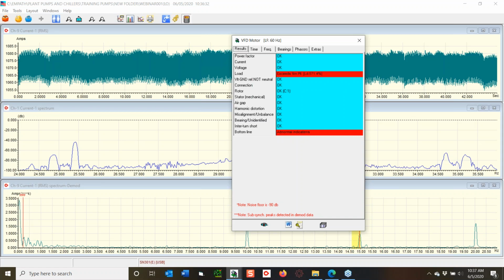So normally what I'll do is, if I get a call and the people have no idea what they're testing — they say we've got 6 motors, they're all 460 volt — I show up and they're not, they're all 4160 volt and there's 7 of them. I can just do it on the fly: collect the data, take pictures of the nameplates, go back, sit down, enter the nameplates into that data, and I'm good.